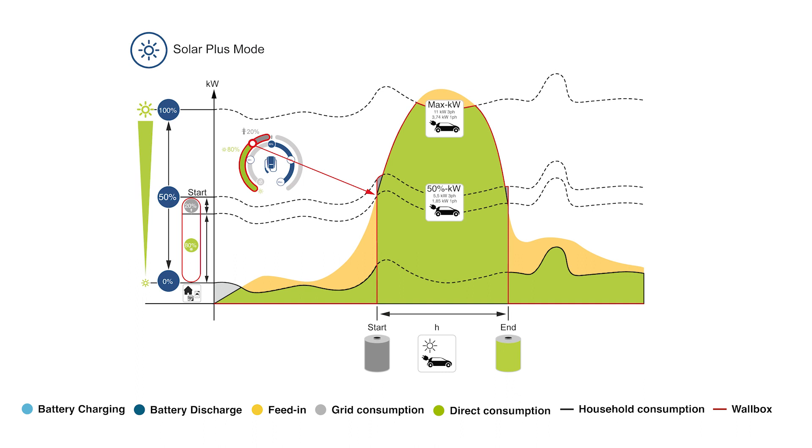In this example, the charging power is 50%. If the PV surplus becomes larger, the main supply is replaced and, in the case of a larger surplus, the charging power is automatically increased to the maximum possible value. Use this mode for small systems with too little surplus PV energy for purely solar charging, or if you always want to specify a certain minimum charging power.